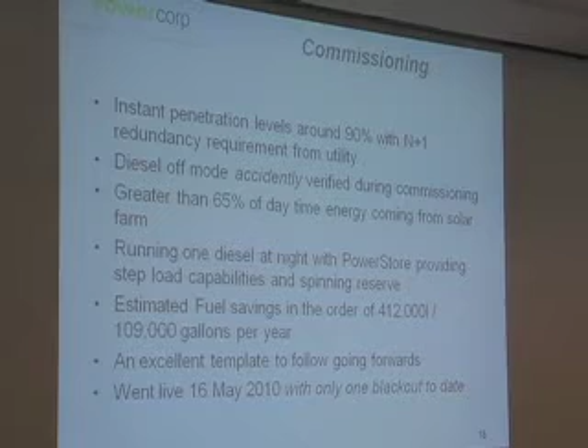Now, that emergency stop is just for the bulk tanks, so he left and the station was still live. He went home on the Friday, and Sunday night everything went black. He went up to the power station to start it, but couldn't get any of the diesels to start. What had happened was the day tank ran out of fuel, then the belly tanks, and the generators ran out of fuel—all four of them. When he turned up to site, he could see each generator had alarms on it. Sure enough, the last 30 seconds of power was held up by the power store, and then it all went black.